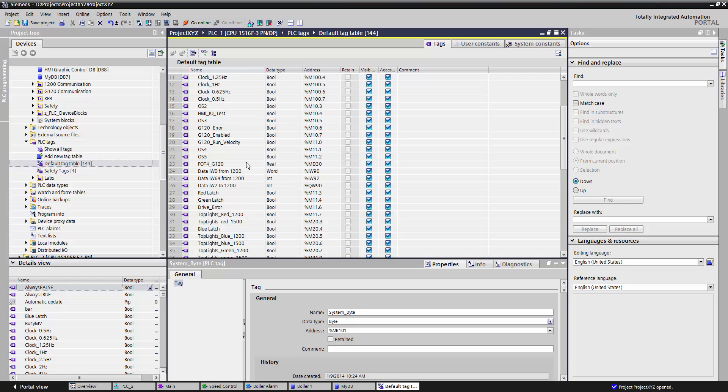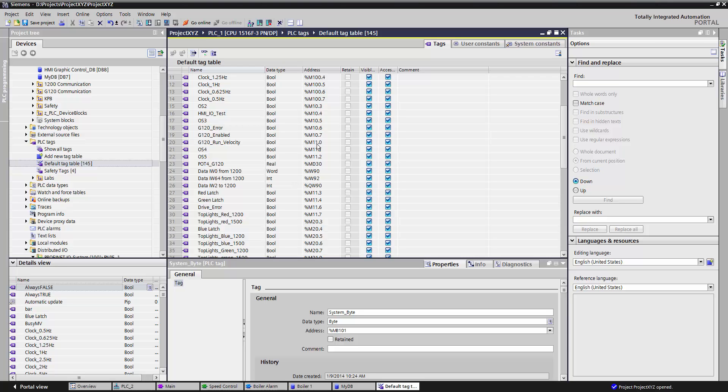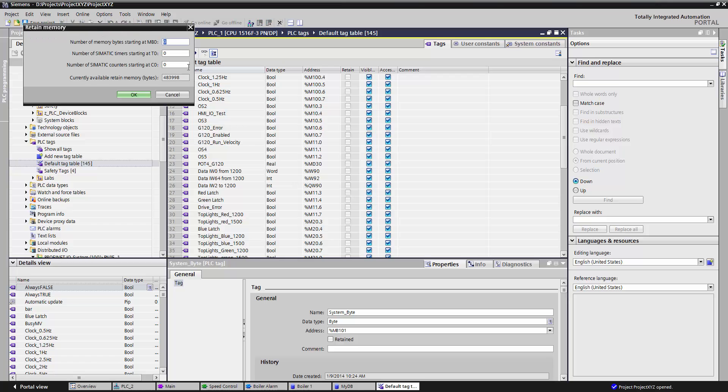In a tag table, the memory data is stored to RAM. That means if the PLC is powered off, this data could be lost. In order to fix this, you can assign an area of memory to be retained. To do that, click on this X icon here, and then give a size for the amount of memory you would like to have retained.